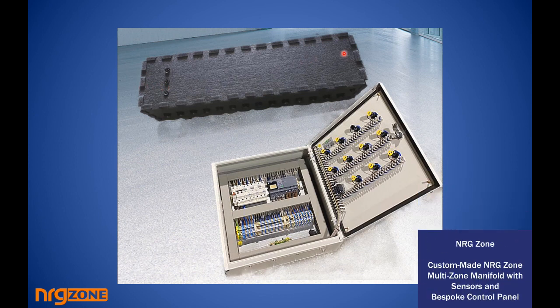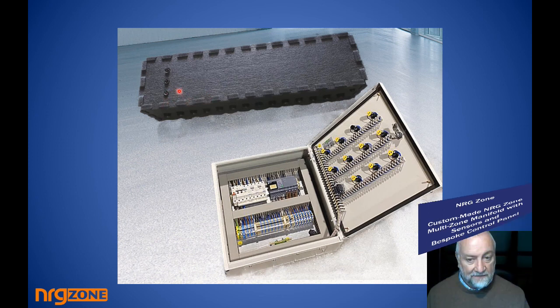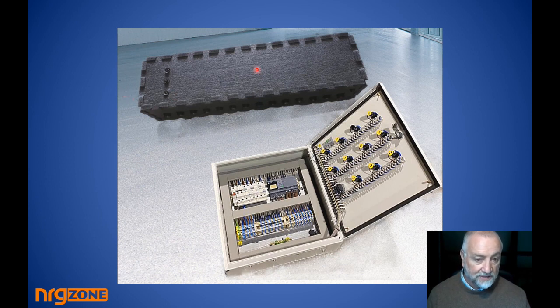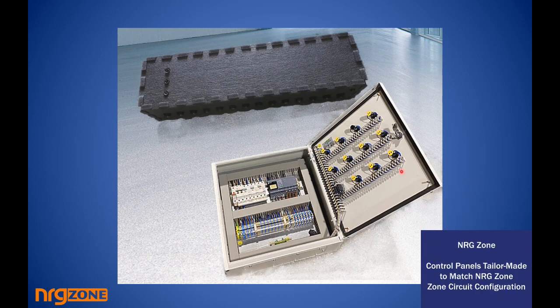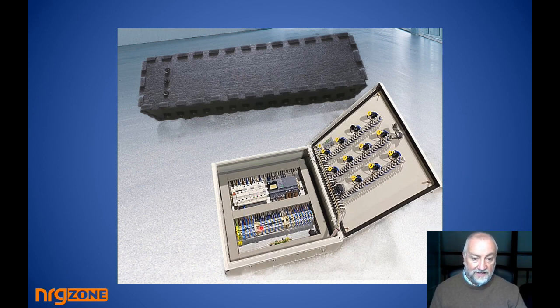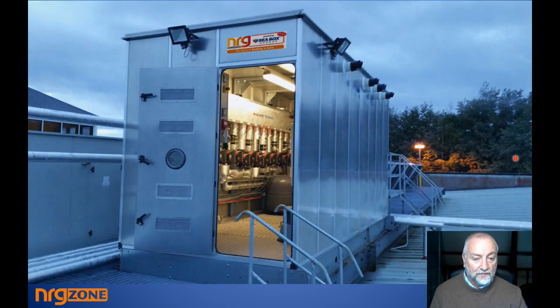Because we make the manifolds and we also make panels, and if you look, this particular panel needed a flow temperature sensor, bypass temperature sensor and a return temperature sensor. The reason was because there was high temperature and there was a heat pump as well, so the control was going to make a difference of what boiler would come in, what appliance would come in, when what zone is called. But again, when we make our panel, we make the MCBs in the panel and the LEDs on the doors and everything, all the wiring, the fusing logic, all comes together to match the numbering of the zones, so that if someone's looking at the manifold and they want to figure out where's the control wire for the 4th zone, it's D. If it was the 3rd one, it's C. So again, very straightforward, logical.